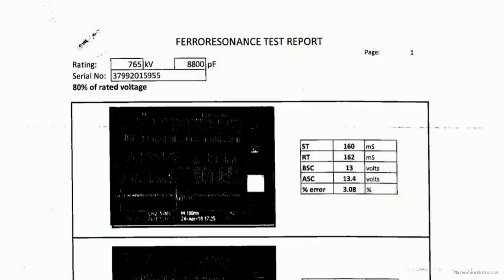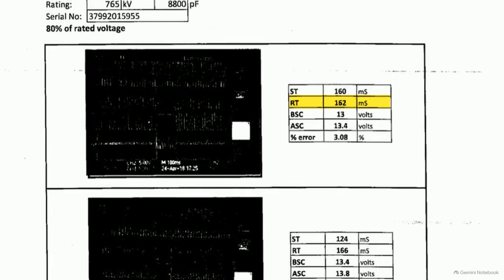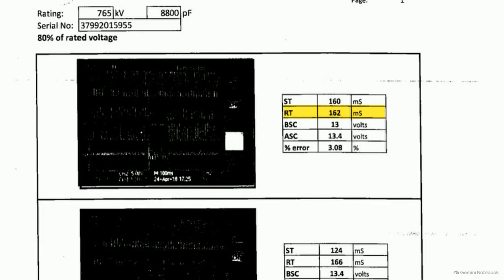This document is a factory ferroresonance test report for a GE 765 kV unit, demonstrating exactly how fast this damping circuit reacts. Look at the top oscillogram. The technicians intentionally subjected the CVT to a short circuit at 80% of its rated voltage. You can see the sudden spike of unstable energy. The table on the right proves the damping circuit engaged immediately. The RT, or recovery time, shows the system tamed the ferroresonance and stabilized the wave in 162 milliseconds.